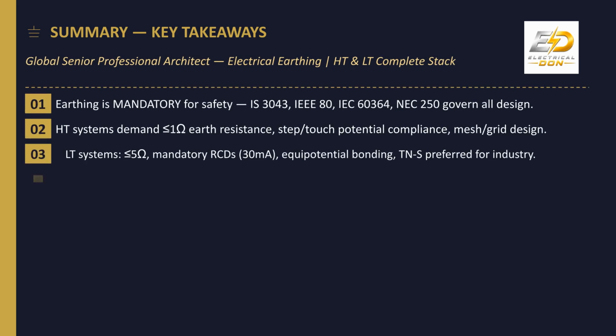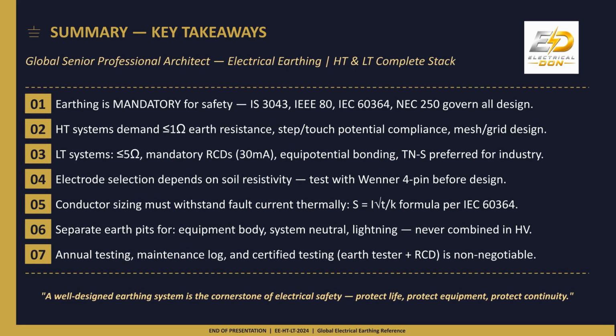In summary, earthing is mandatory for safety, governed by key international standards. HT systems require robust design and low resistance, while LT systems mandate RCDs and equipotential bonding. Selection must be based on soil resistivity, and conductor sizing must withstand fault current. Annual testing is non-negotiable. A well-designed earthing system protects life, equipment, and continuity.